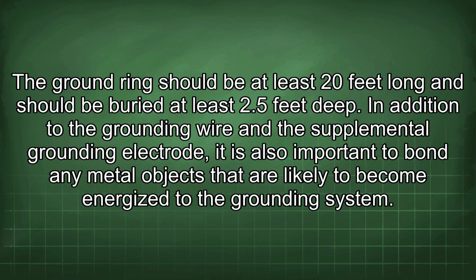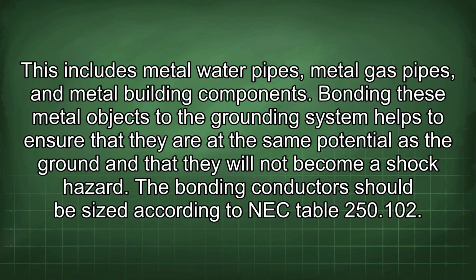In addition to the grounding wire and the supplemental grounding electrode, it is also important to bond any metal objects that are likely to become energized to the grounding system. This includes metal water pipes, metal gas pipes, and metal building components. Bonding these metal objects to the grounding system helps to ensure that they are at the same potential as the ground and that they will not become a shock hazard. The bonding conductors should be sized according to NEC Table 250.102.